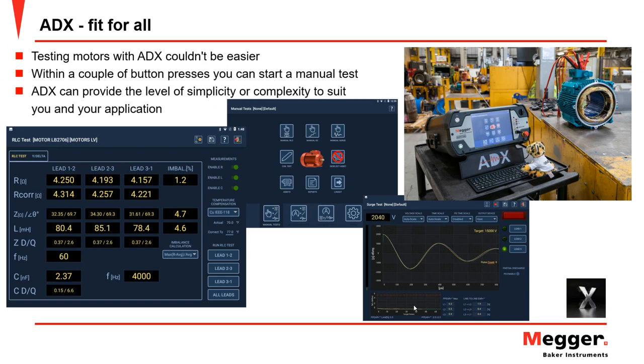Whereas the surge test, which is the sine wave test that you see at the bottom there, gives us the opportunity to see what's happening to the motor during startup. And if there's any weakness or fluctuation in that insulation, we can continue to operate the motor, but we know it's there. We can then start to trend the condition to see how far the motor can run before it gets to the point where we have to pull it out. So that's the strength of this tester. It enables us to head off any unwanted costs through downtime.